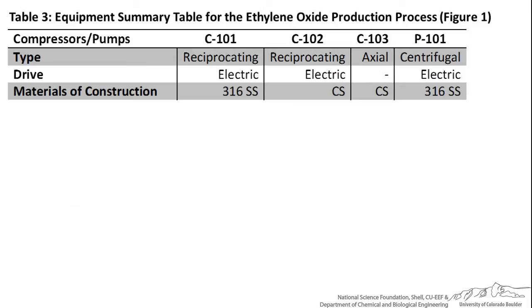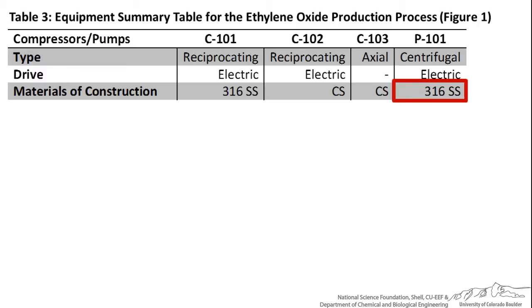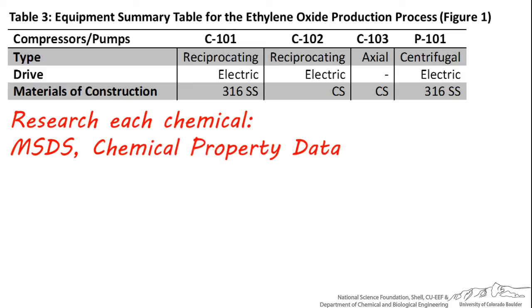For our ethylene oxide process, oxygen is a common oxidizer, so I chose 316 stainless steel for this compressor. I felt that carbon steel was more appropriate for the ethylene stream going through C102, since it's not as reactive with metals. I chose carbon steel for the turbine, which has CO2 and oxygen flowing through it, since this stream is fairly inert and shouldn't cause significant oxidation. I chose 316 stainless steel for this pump, since it has a very high concentration of ethylene oxide going through it — however, as a mild oxide, it's not as reactive as a strong acid or base, so I don't feel that using a nickel alloy would be necessary. These materials were chosen only after doing quite a bit of research on the chemical properties and reactivity of these chemicals.